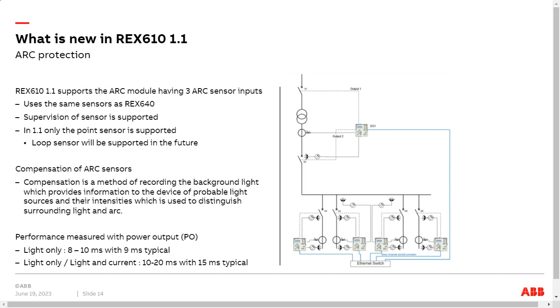So, for example, if there's a sudden change of light, but it's still within this background light criterion, it will not operate. I can also say that it's not a trigger point such that if the light exceeds this, it will trigger. As I said, it's a multi-criteria function, and this is one criterion, for example. So this also improves the reliability of this ARC protection.